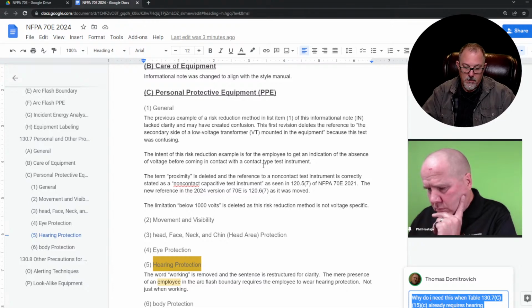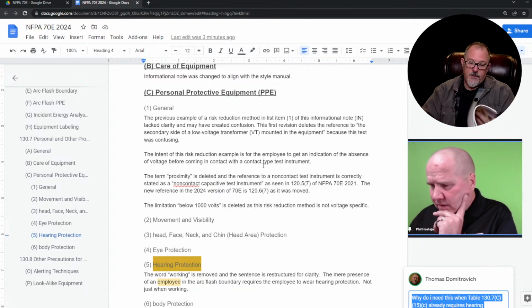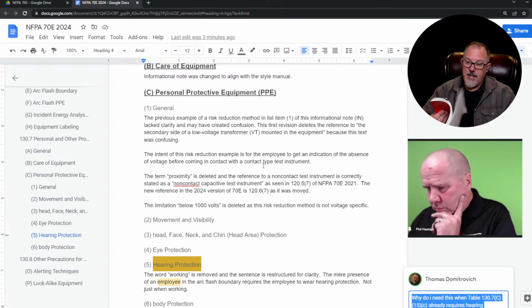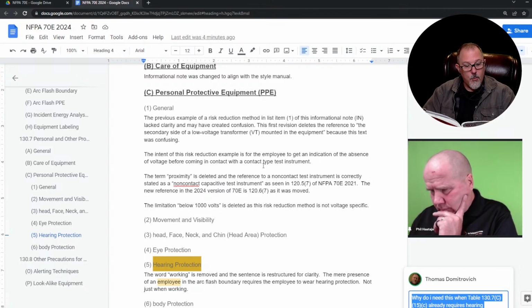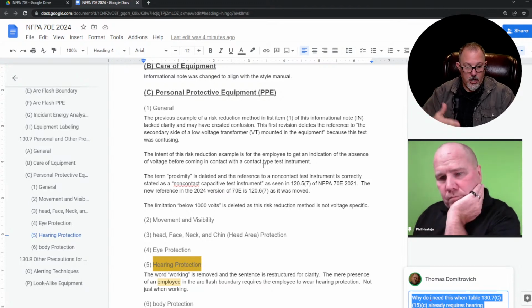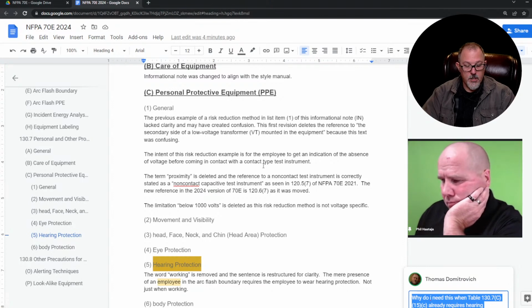Well, that's different, though. Hold on. That's different because that's outside of the table, because the table says no more than 4 calories. But what 130.5C6 tells you is the threshold is 1.2. If you're below 1.2 calories, you do not need to wear arc-rated clothing. So that's outside of that table.